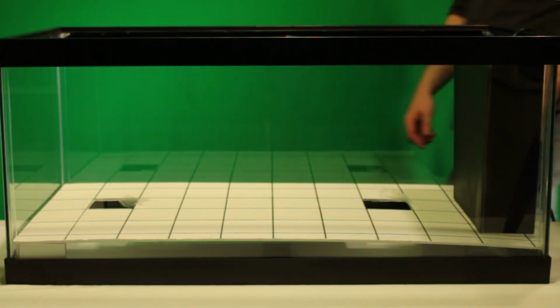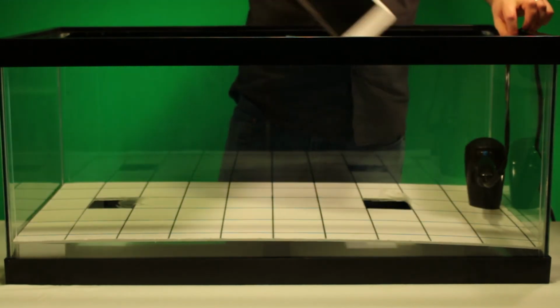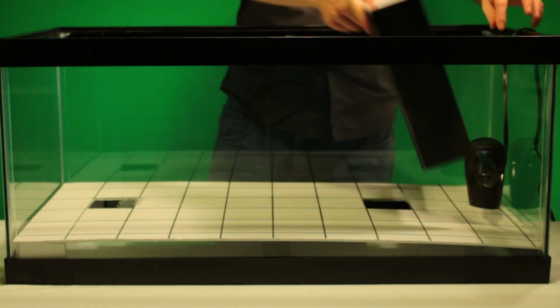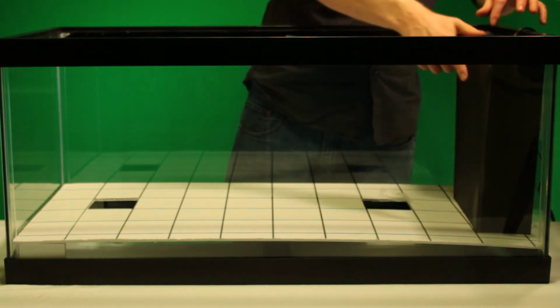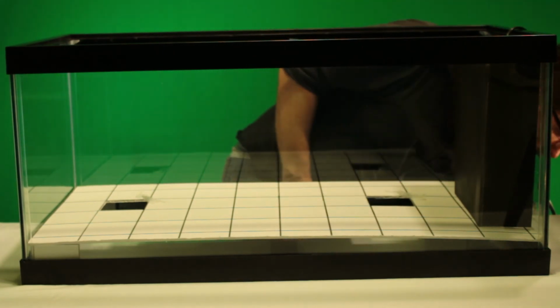Back at our data center, the velocity of the air close to the CRAC unit caused that negative pressure we talked about earlier. Let's look at this in practice. So here we are at our raised floor fish tank data center. Here's our CRAC unit. Here are two open tiles. Then I'm going to put this piece of paper over the nearest vented tile to the CRAC.